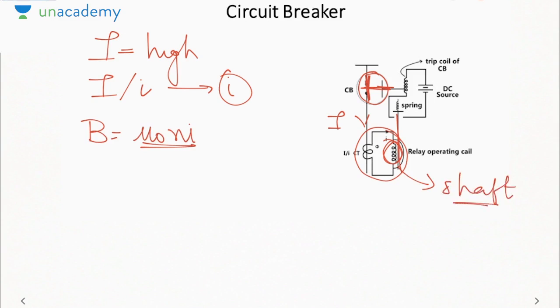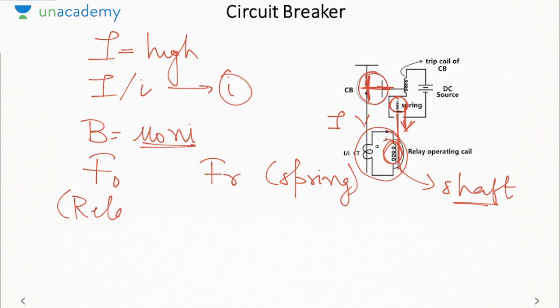It will attract this, so this will be forced to be pulling down. But this spring will try to stop it. So there are 2 forces. One is your operating force, the other is your restraining force. This is provided by the spring. This is provided by the relay operating coil. Whenever the operating force is greater than the restraining force, this shaft will be pulled down.